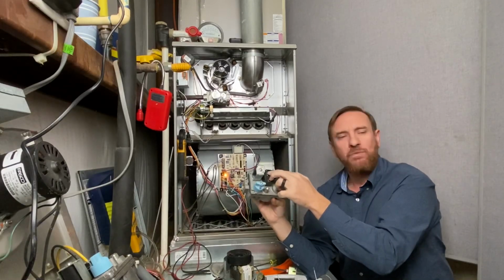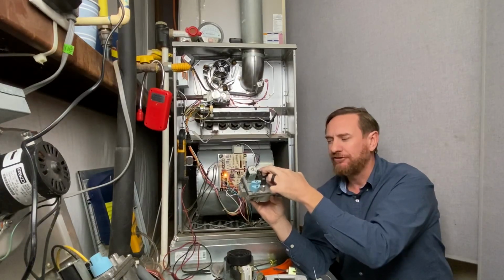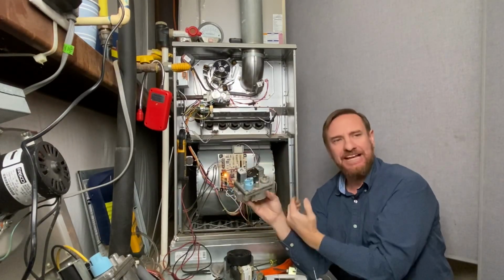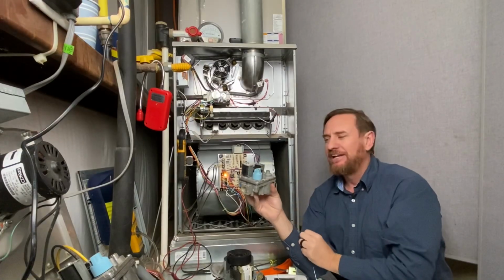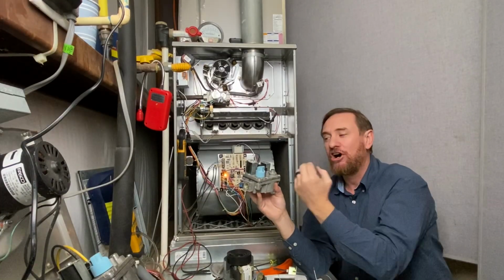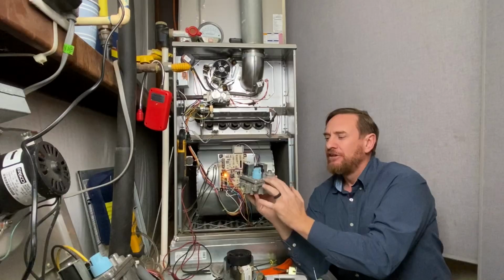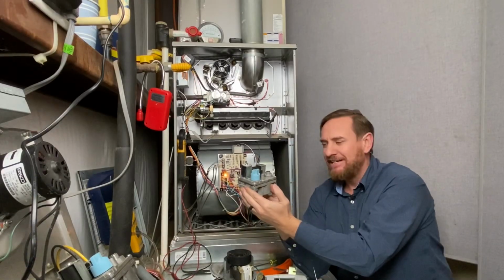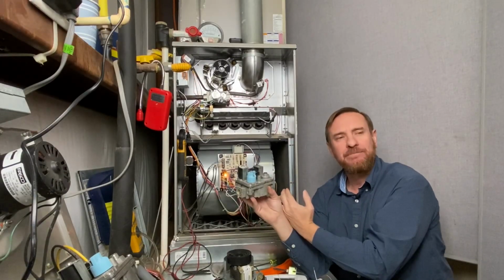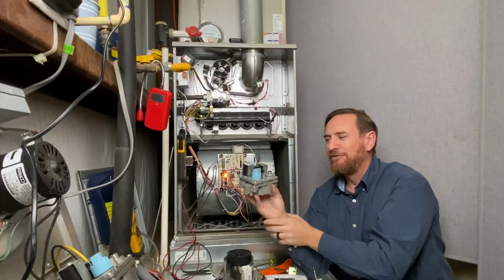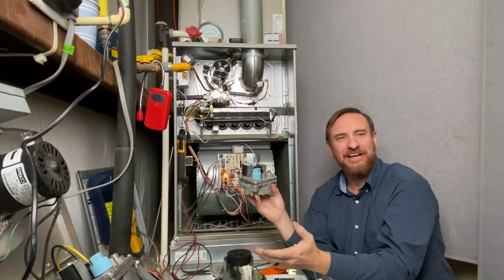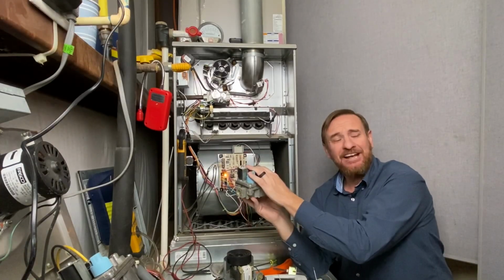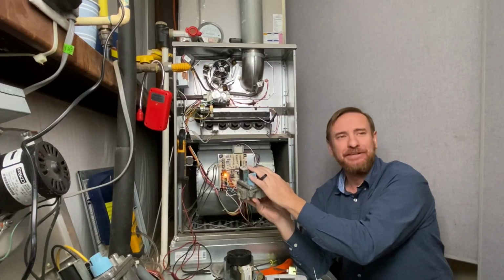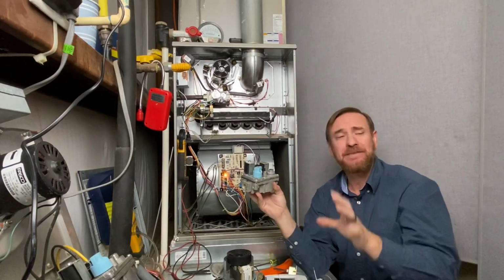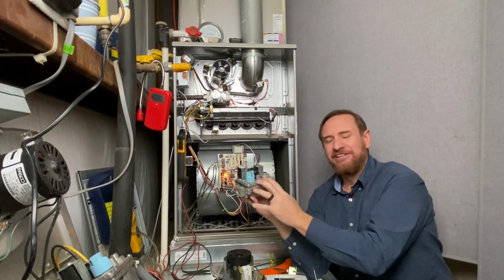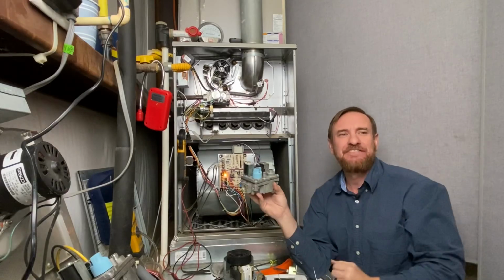But we have these 2 wires that come in here. When 24 volts go, it opens this valve and allows gas to flow. The reason I want you to call it a combination gas valve is because it's also a pressure regulator. So you've got to make sure you have gas pressure coming in and then it's reducing it to the correct amount of pressure coming out. I've had technicians before that go to customers' houses and diagnose a bad gas valve, and the real reason is the customer didn't pay the gas bill, or something happened with the gas bill. Now they're trying to sell them a new combination gas valve and they don't have any gas to the house.